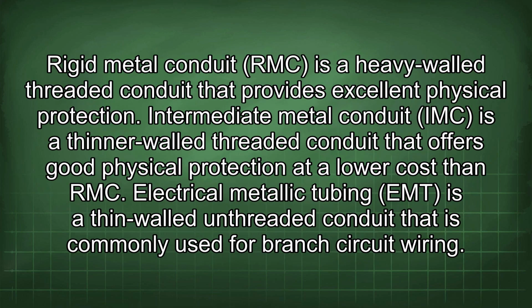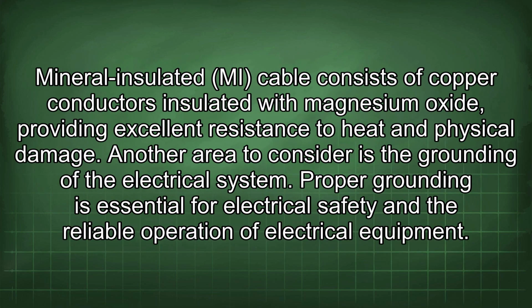Rigid metal conduit (RMC) is a heavy-walled threaded conduit that provides excellent physical protection. Intermediate metal conduit (IMC) is a thinner-walled threaded conduit that offers good physical protection at a lower cost than RMC. Electrical metallic tubing (EMT) is a thin-walled conduit that is commonly used for branch circuit wiring. Mineral insulated MI cable consists of copper conductors insulated with magnesium oxide, providing excellent resistance to heat and physical damage.